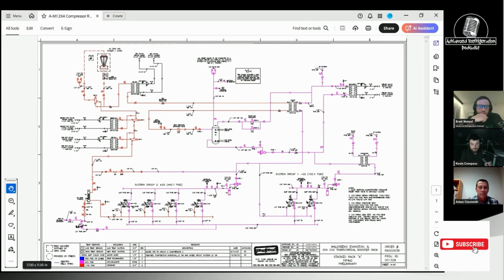So this rack is connected to a ground loop, which then we scavenge heat out of it and basically turn this into a heat pump in the wintertime. That warm water mixes with the chilled glycol, and the chilled water loop then produces an artificial load to ramp up the refrigeration and produce the heat we need. So that's a little bit of background story on this, and I'll walk through the P&ID.